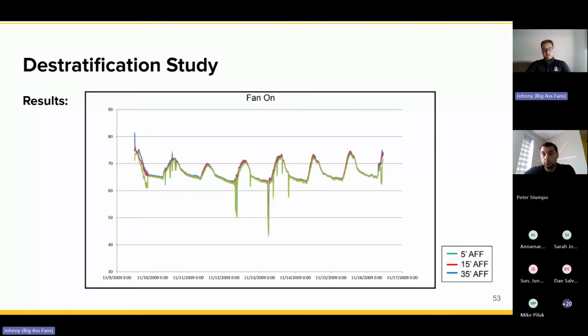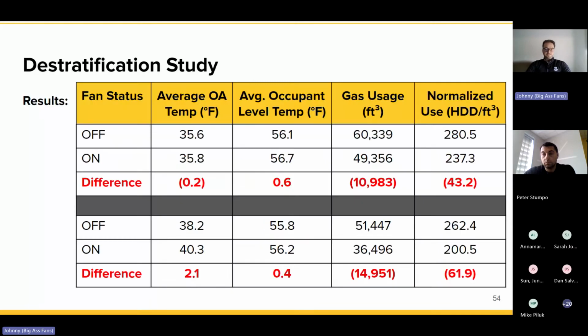Just keep that in mind, and what that translates to is some significant gas reductions. What you're seeing is 2 tests, the top portion and the bottom portion. We ran this over 2 separate weeks just to make sure that we're doing this accurately and getting good data. The thing to pay attention to here is that the outside air temperature did not really change. The occupant level temperature was neutral because we want to maintain a certain set point. And the gas usage is where we really saw a reduction.